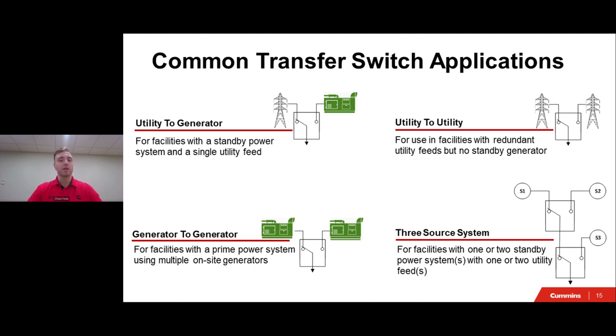Next up in the top right of this slide is utility to utility. This is a very similar concept to what was mentioned just before this as gen to gen. So you'll have a facility that is being supplied by two redundant utility feeds, and then you will have that automatic transfer switch being used to monitor the power of both those feeds and transfer power between the two if needed.